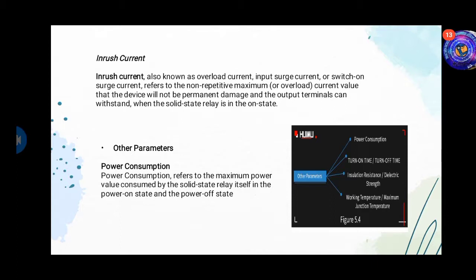Inrush current, also known as overload current, input surge current, or switch on current, refers to the non-repetitive maximum current value that the output terminal can withstand without permanent damage when the solid state relay is in the on state. Other parameters: power consumption. Power consumption refers to the power consumed by the solid state relay itself, when the power is on and off.